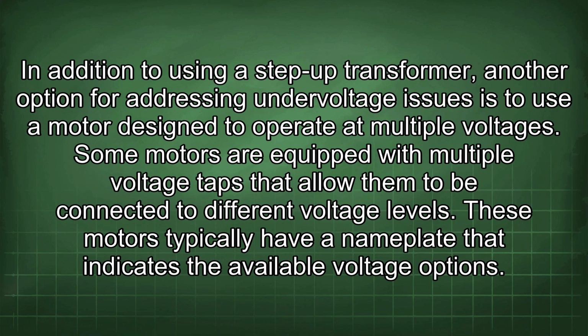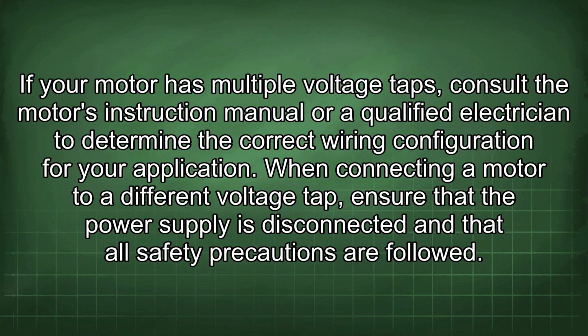In addition to using a step-up transformer, another option for addressing undervoltage issues is to use a motor designed to operate at multiple voltages. Some motors are equipped with multiple voltage taps that allow them to be connected to different voltage levels. These motors typically have a nameplate that indicates the available voltage options. If your motor has multiple voltage taps, consult the motor's instruction manual or a qualified electrician to determine the correct wiring configuration for your application.